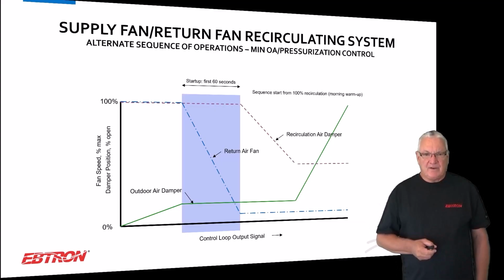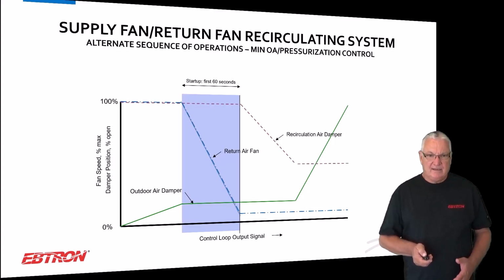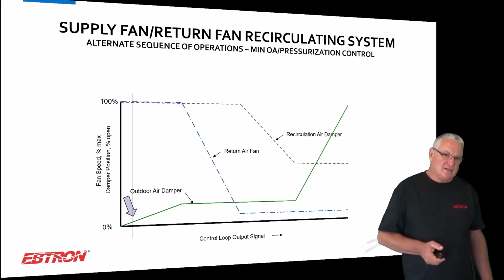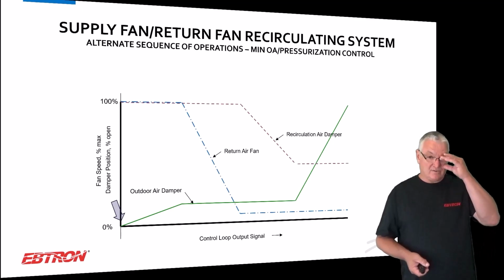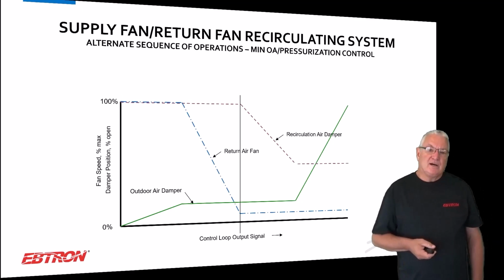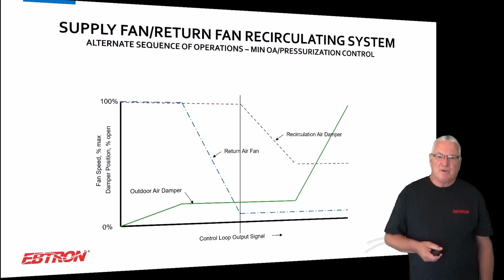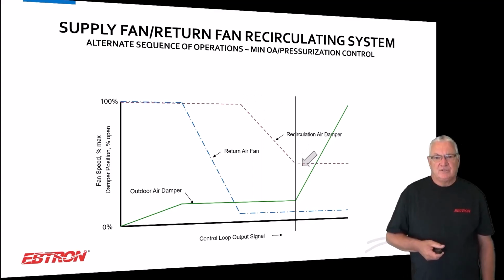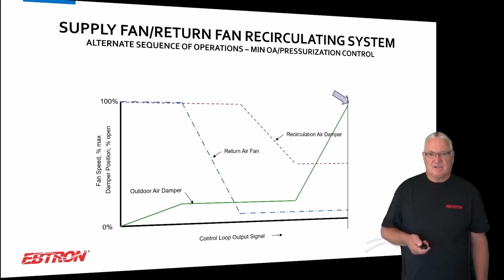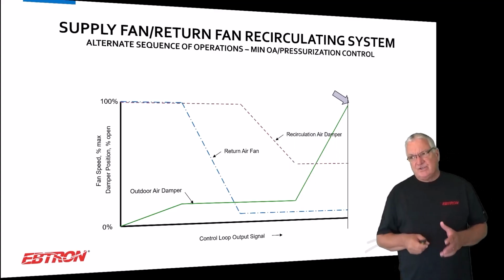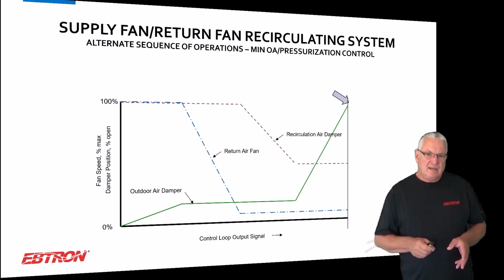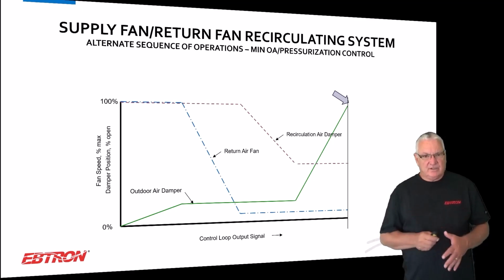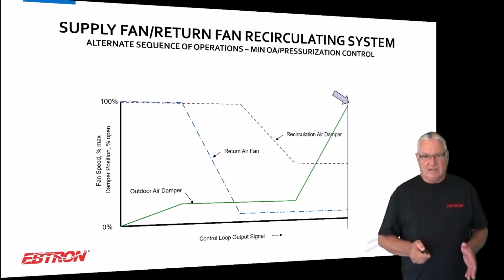But instead of everything being the same, using the return air fan as we discussed during startup, being in this one range, and then if you had too much outside air, closing the outside air damper, which could be a real challenge if it's an oversized or poor condition damper, the next part of the sequence, instead of opening the outside air damper, you actually use the recirculation air damper to bring more outside air in. So you're keeping that outside air damper fixed longer, and then hopefully you're really not in this range where you have to start to control that damper. This strategy makes the outside air damper less critical to your control. Okay, they both work fine. You can make arguments for both.